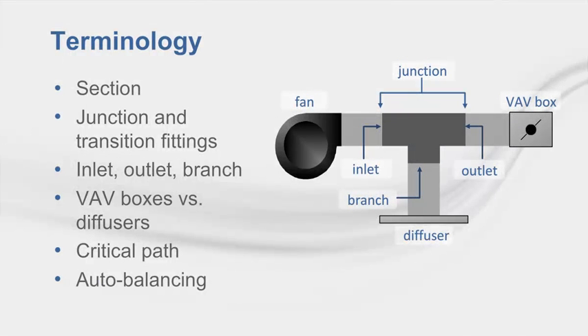To use Duct Designer you'll need to understand the terminology used in the application. A section is all ductwork from the inlet of a junction or transition fitting to the inlet of the next downstream junction or transition fitting. A root section is connected directly to the supply fan outlet. Junction and transition fittings connect the sections of ductwork. Inline fittings join, adjust, or adapt other duct system components within duct sections.